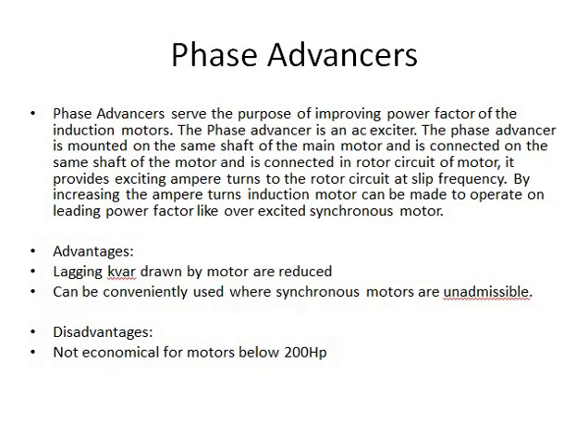Phase advancers. Phase advancers serve the purpose of improving the power factor of induction motors. The phase advancer is nothing but an AC exciter, mounted on the same shaft as the main motor and connected in the rotor circuit of the motor. It provides exciting ampere turns to the rotor circuit at slip frequency.